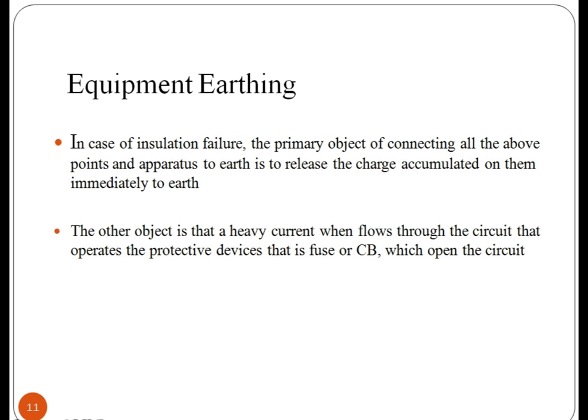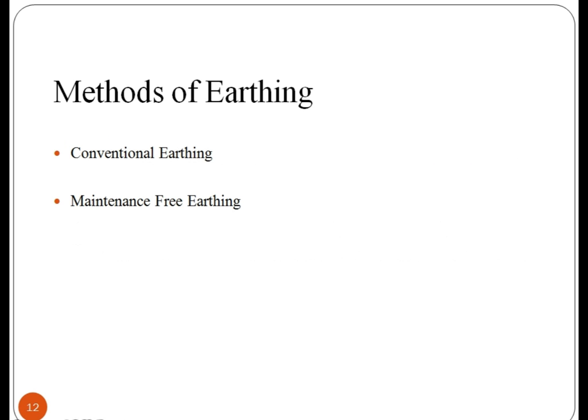When insulation failure occurs, the primary object of connecting all points and apparatus to earth is to release the charge accumulated on them immediately to earth so that a person coming in contact may not experience an electric shock. The other object is that a heavy current flowing through the circuit operates the protective devices, that is, the fuse, which opens the circuit. What are the methods of earthing? There are two types of earthing: conventional earthing and maintenance-free earthing. Let us study these methods in detail.